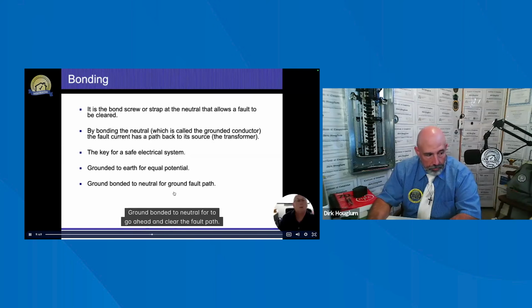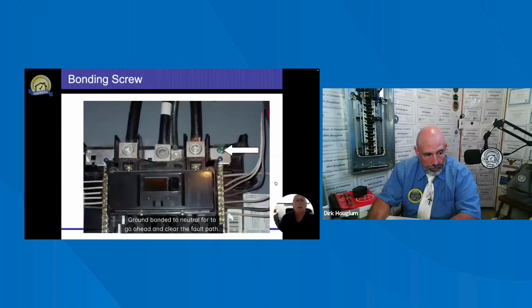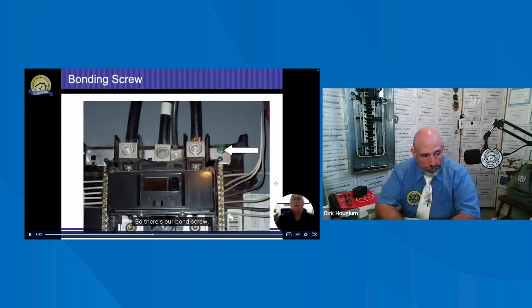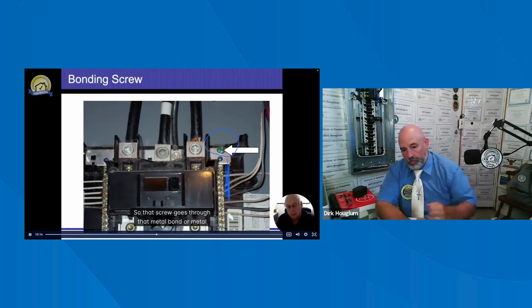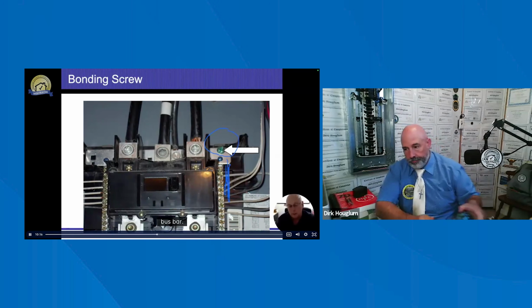Ground bonded to neutral to go ahead and clear the fault path. Good. So there's our bond screw, and these are just different examples of what we're going to see on the bond. And again, we're tying right below that. It's going to be my neutral bus bar. All right. So this whole thing over here is my neutral bus bar. And there you can see where my bond screw is. So that screw goes through that metal bus bar.